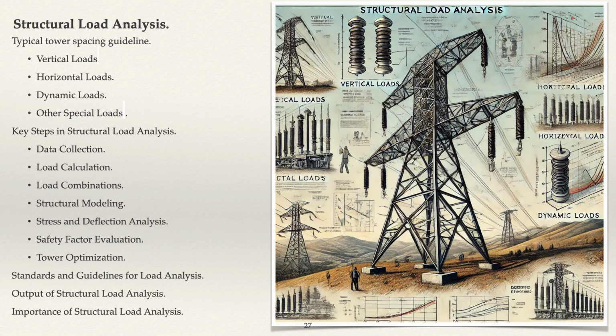Structural load analysis. Structural load analysis is a critical process in the design and construction of transmission line towers. It involves determining the various forces and stresses acting on the tower and ensuring the structure can safely withstand them over its operational lifespan. This analysis ensures that the tower remains stable under normal conditions and extreme environmental loads, providing safety and reliability. 1. Typical tower spacing guideline. 2. Key steps in structural load analysis. 3. Standards and guidelines for load analysis. 4. Importance of structural load analysis.